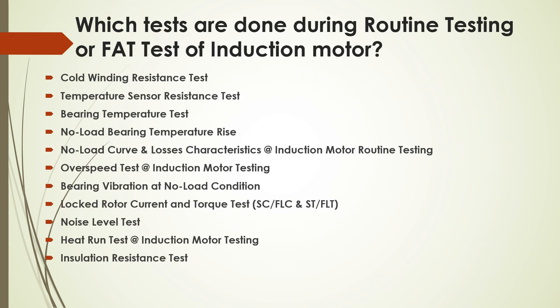Which tests are done during factory testing (FAT test) of an induction motor? These include: cold winding resistance test, temperature sensor resistance test, bearing temperature test and no-load bearing temperature rise, no-load curve and characteristic losses, overspeed test, bearing vibration at no-load condition, locked rotor current and torque test, noise level test, heat run test, and insulation resistance test.